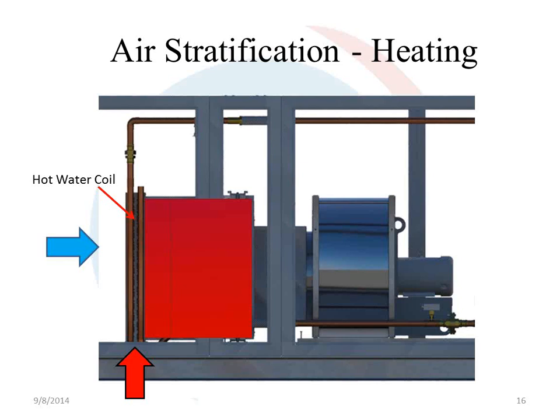Alright, this is a little diagram, and you can see here's the heating coil. Now on the heating coil it does maintain a 1 degree plus or minus temperature difference, but in the fan section it does a lot of mixing, so in the discharge you have a plus or minus 0.5 degree temperature difference. And what does this do for you? Well, it helps you reduce the risk of inaccurate sensor reading with the duct sensors. And also, since you reduced that large delta T, you've reduced customer complaints.